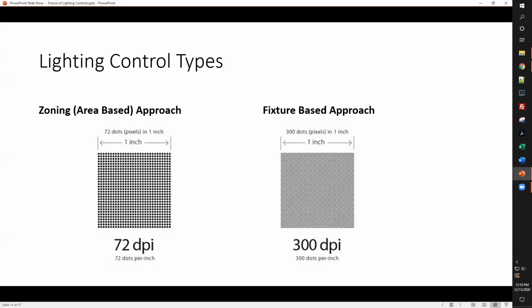The fixture-based approach is the opposite, where you imagine every light in that open office area has an occupancy sensor, a photo cell, or an air temperature sensor, etc. That increases the amount of data we're receiving in a space, and we get a much clearer image. So if each of those light fixtures had a thermal camera or an air temperature sensor, then we could get a gradient heat map of what the room temperature is like.